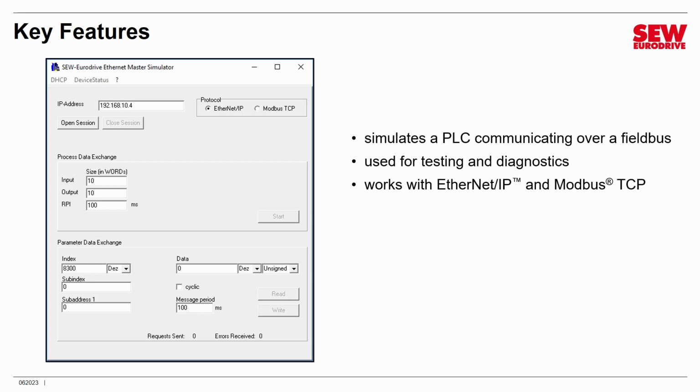It works either with Ethernet IP or Modbus TCP field buses, so you can use it only with those two. This does not work with Profinet or any of the older classic field buses. So if you have a different field bus, then you'll have to get a diagnostic tool elsewhere. But this one is good for these two, and these are very popular field bus standards. So it just sends POs to the device, and it monitors the PIs coming back from the device. Very simple. You'll be able to learn this in just 5 minutes.